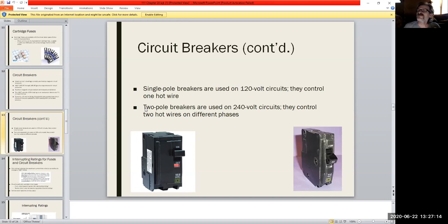So pretty much you have to think about what you've got going in your house. Okay, I've got two different 120 lines coming in and a neutral. Neutral, of course, is not going to get a circuit breaker of any kind. So very typically, the most populous breakers I'm going to have in my panel are going to be single pole breakers, meaning one line. Okay, single pole, 120 volts.